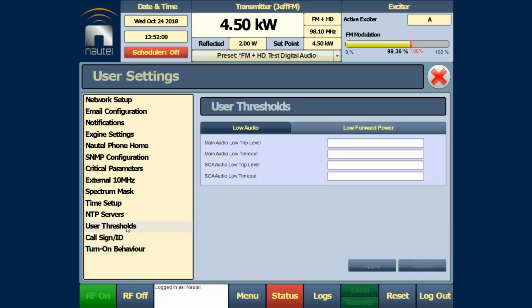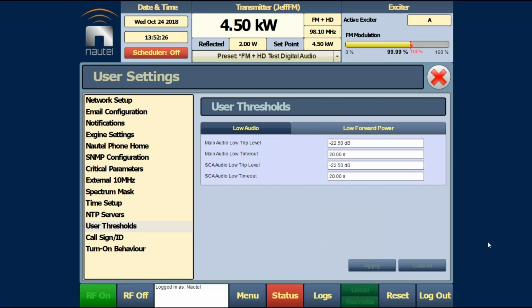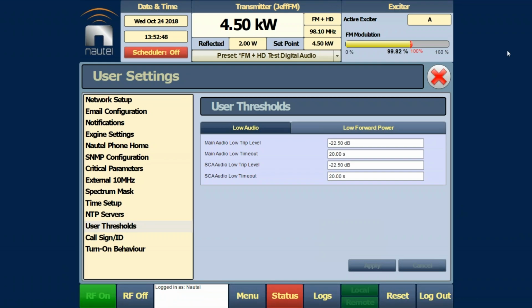I know you wanted to mention user thresholds — something a lot of people aren't aware of. With the audio switching circuitry and the revert to normal, you have the ability to set, for both main and SCA audio, exactly where those trip levels are. Same thing on the low forward power tab: you can tell it at what point the power is low enough that the transmitter should send an alarm. For example, in the US, if you wanted an alert every time you're below 90%, which is the minimum level by FCC decree, the transmitter can send you an email whenever forward power drops below 90% of assigned.